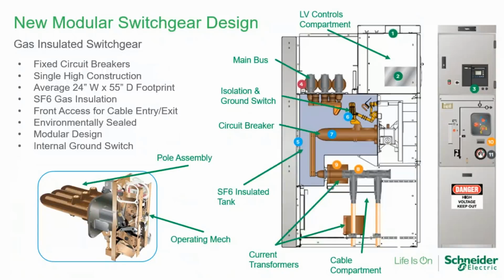If we look at newer designs of medium voltage switchgear, this is an example of gas insulated switchgear. So one of the first big differences here is with the newer styles of switchgear, we're looking at fixed mounted circuit breakers as opposed to withdrawable circuit breakers. And the trade-off there being obviously the maintenance factor, the ease of withdrawing the circuit breaker in order to get to it and operate it.